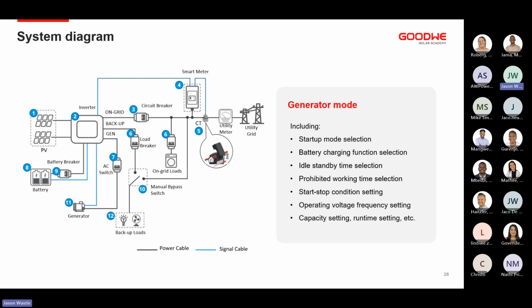On the SolarGo app, in generator mode, you'll be able to control the start-stop settings, idle standby times, and prohibited working time selections. You can also set parameters on your capacity settings and runtime settings, and set the battery charging function should you want to charge the batteries through generator mode. Like I said, you can also set your power limits for your generator, so you can use a bigger generator for a smaller inverter in theory.